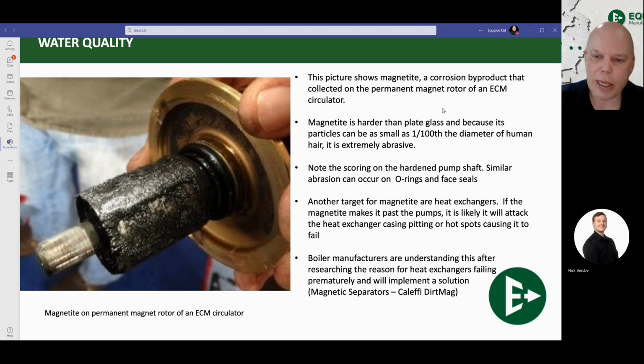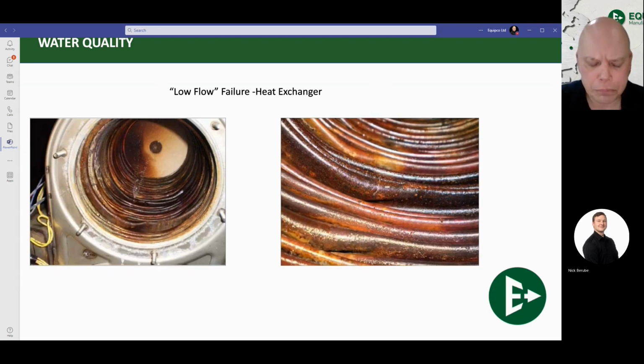That's your magnetite, and that we really want to get out of a system because it's going to cause detriment to our two most important parts. If we don't heat it, then we can't get the heat out of it. We're not going to heat our home. And if we can't flow it, we can't distribute the heat, so we're not going to be able to heat the home. Magnetite is the very first piece of a system that's going to go cataclysmically wrong, and the only way to get that out is with magnetic separation. So that's one thing to keep in mind with regards to the trim that we're going to be talking about.